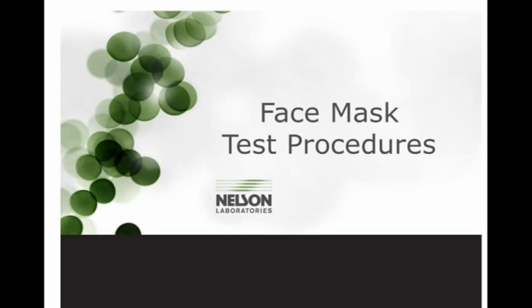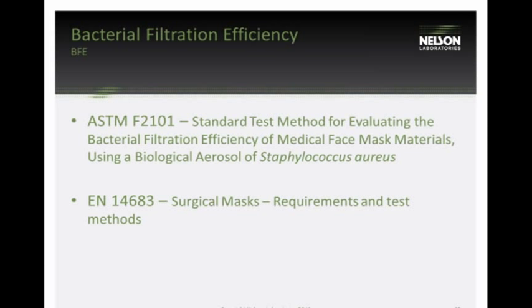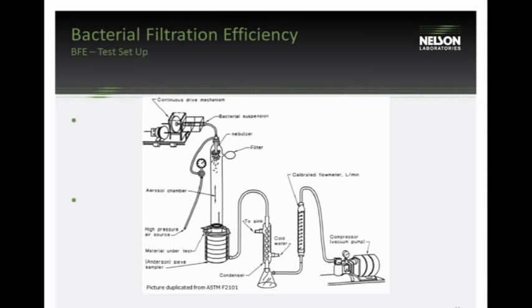That concludes the first half of the presentation on gown and drape testing. Now moving to face mask testing, starting with the BFE test — Bacterial Filtration Efficiency, laid out in ASTM F2101 and EN 14683. An important note: F2101 is a medical face mask material test. If fit is an issue, such as with respirators, NIOSH-type testing is the more appropriate direction. For face mask materials, BFE is the standard approach.